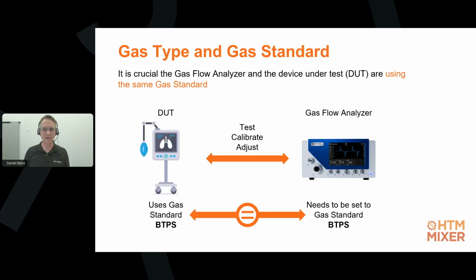Different ventilator manufacturers use different gas standards. The most common ones are called STPD and BTPS. BTPS is usually for ICU vents, and STPD more for things like BiPAP machines and more basic ventilators. So you need to figure out what gas standard is used by the device under test and then set the same gas standard on your gas flow analyzer. On all gas flow analyzers out there in the field, you have different ones to choose from, so you will find the ones you need. Most vent manufacturers specify the gas standard used in their technical documentation. Otherwise, they will be able to tell you when you ask them.